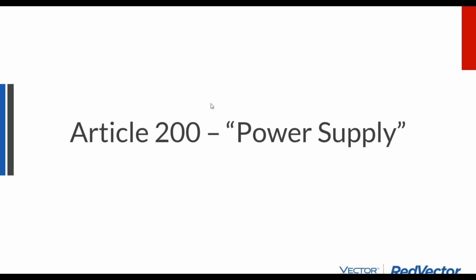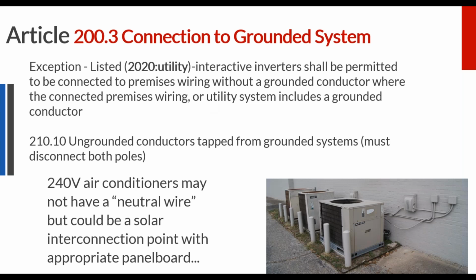Article 200. So now, or really chapter 200, is getting into the power supply issue. So we're going to start out with a definition of a grounded system. It's connected to ground. The alternate is an ungrounded system. It's an advanced issue, but it has to do with how you can have a reference voltage potential rather than establishing the negative to ground or the positive to ground. And there's different ground fault detection requirements and positives and negatives for both. So generally speaking, there's this newer kind of grounding methodology called floating on the DC side, which is to not ground either side, but to put overcurrent protection on both ends.